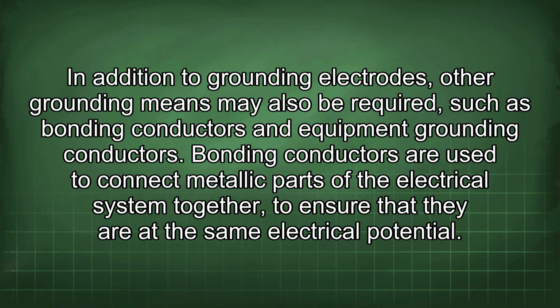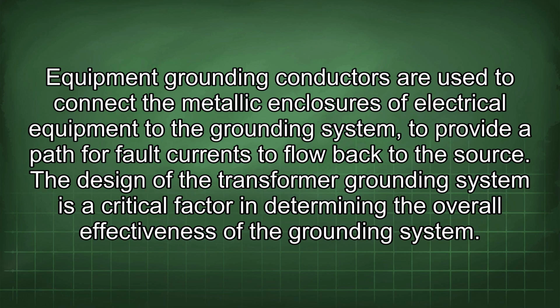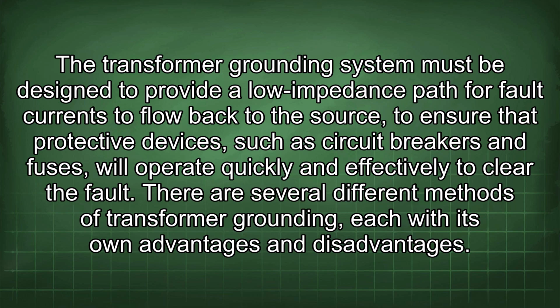In addition to grounding electrodes, other grounding means may also be required, such as bonding conductors and equipment grounding conductors. Bonding conductors are used to connect metallic parts of the electrical system together to ensure that they are at the same electrical potential. Equipment grounding conductors are used to connect the metallic enclosures of electrical equipment to the grounding system to provide a path for fault currents to flow back to the source. The design of the transformer grounding system is a critical factor in determining the overall effectiveness of the grounding system. The transformer grounding system must be designed to provide a low impedance path for fault currents to flow back to the source to ensure that protective devices, such as circuit breakers and fuses, will operate quickly and effectively to clear the fault.